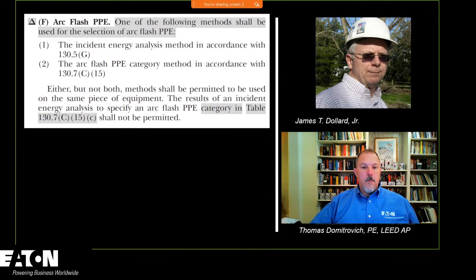When you go into 130.7 C15C, we tell you that you're going to estimate the available fault current. You're going to estimate the clearing time. And when you're doing that, it's relatively easy for us to estimate available fault current. We can go to the next transformer upstream. There are calculators, Tom, like the one you have, and we can assume an infinite primary on the transformer, and we get a number. We get a maximum number.